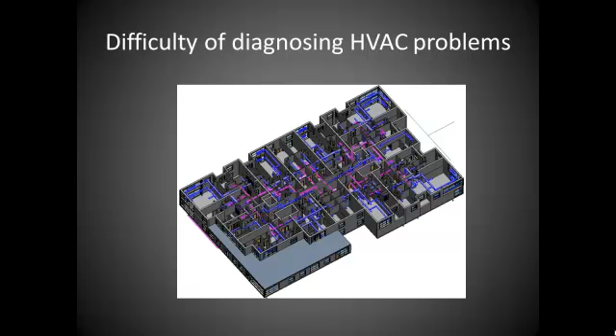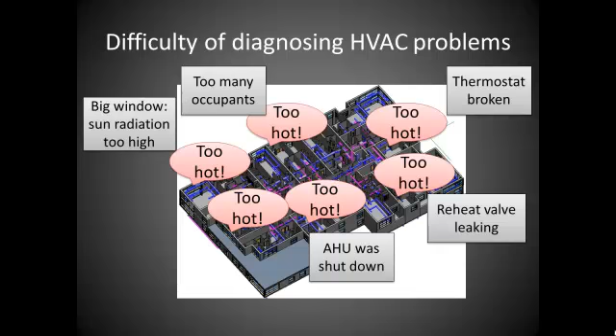For example, for a 'too hot' problem, in one space it could be because the room has big windows and sun radiation is too high. In another space, it could be because of too many occupants. In other spaces, it could be failure of HVAC components such as thermostats or reheat valves. It could be because of unusual operational activities such as shutdown of an air handling unit. It could also be as simple as an air diffuser being too close to an occupant.